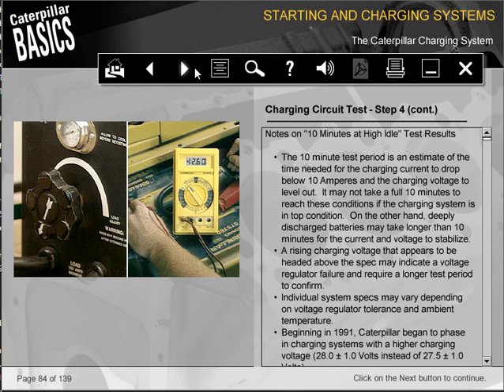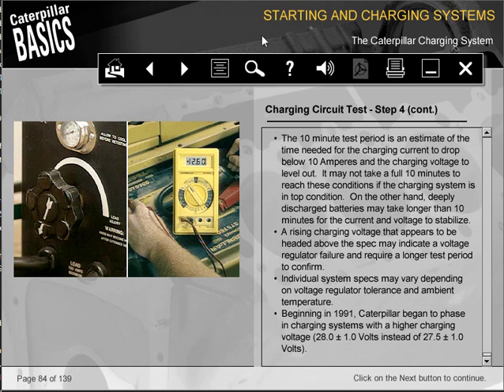A rising charging voltage that appears to be headed above the spec may indicate a voltage regulator failure and require a longer test period to confirm. Individual system specs may vary depending on voltage regulator tolerance and ambient temperature. Beginning in 1991, Caterpillar began to phase in charging systems with a higher charging voltage, 28.0 plus or minus 1.0 volts, instead of 27.5 plus or minus 1.0 volts.